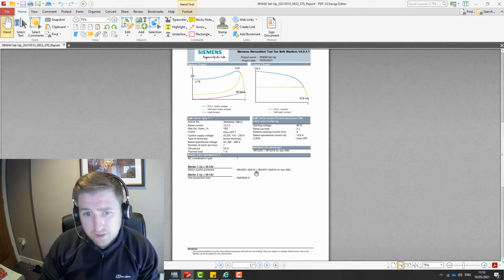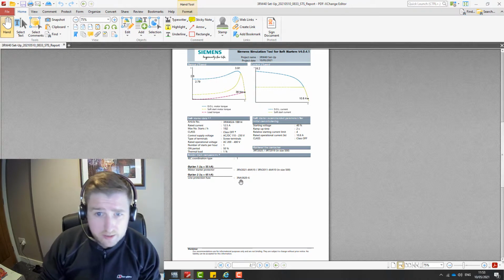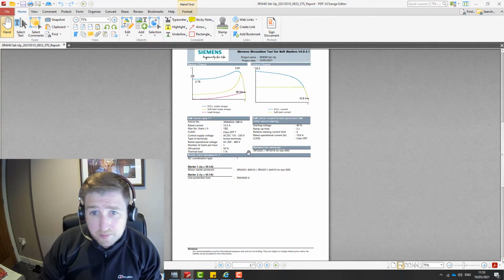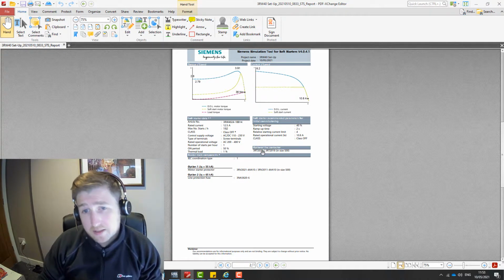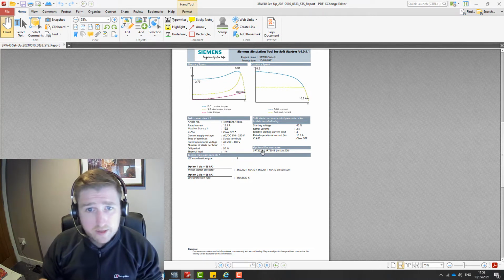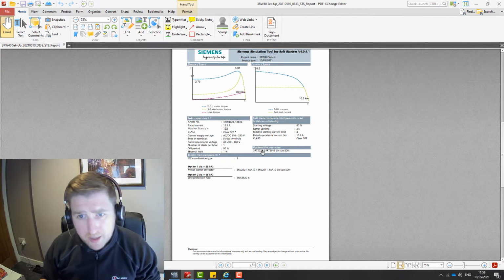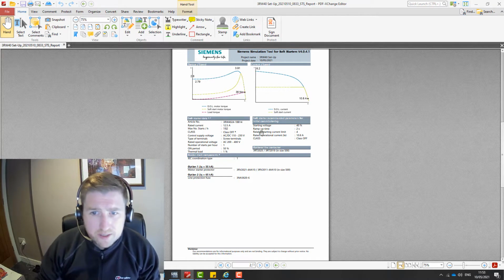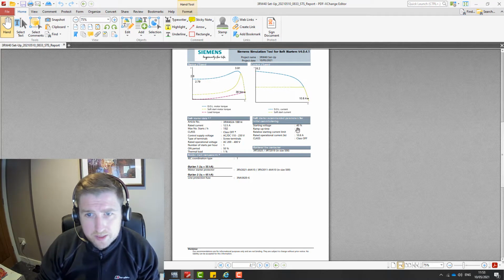It gives you options for motor circuit breakers or fuses. It even promotes an optional line contactor, but that's not necessarily required. It is optional because the device has an integrated bypass. And then it gives you the starting parameters here, which it suggests for that particular application. So it gives you all the information that you can then include in your project and what you need to set those parameters to.